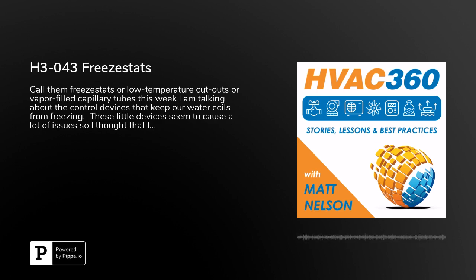It's not necessary. They're not going to burst. So this is only talking about water coils. If you only have a cooling coil, it's going to go on the downstream side of that. Alternately, if you have only a heating coil, it's going to go on the downstream side of that, regardless. So that's where you're going to want to put it.